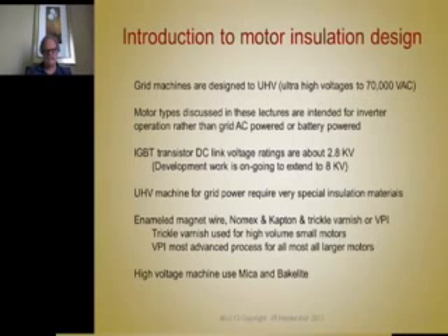I don't know what the status is, it's not my expertise, but ultra high voltage machine insulation systems for grid power require very special insulation materials, which we're not really going to discuss here. For the machines that we're going to talk about, we use enameled magnet wire for insulation from conductor to conductor, turn to turn, and then Nomex and Kapton slot liners, and then varnishing using VPI or trickle varnish techniques. Trickle varnish is very widely used for high volume motors, and seems to work well.